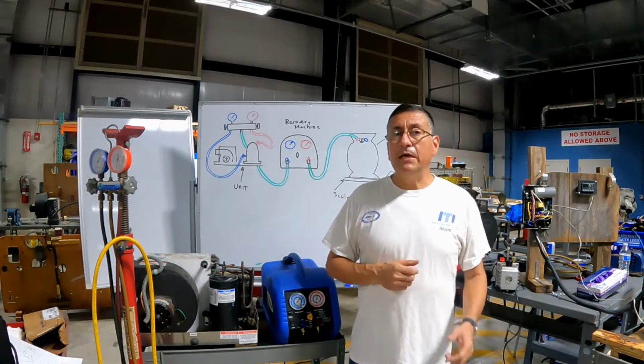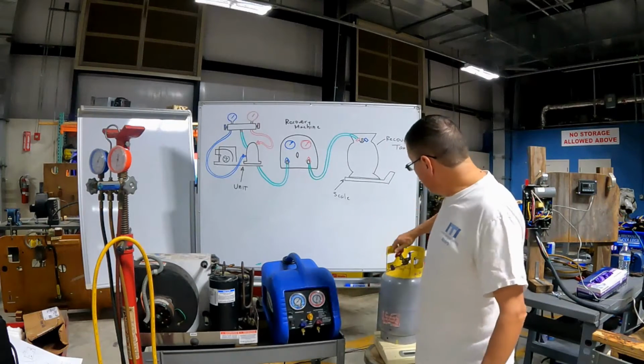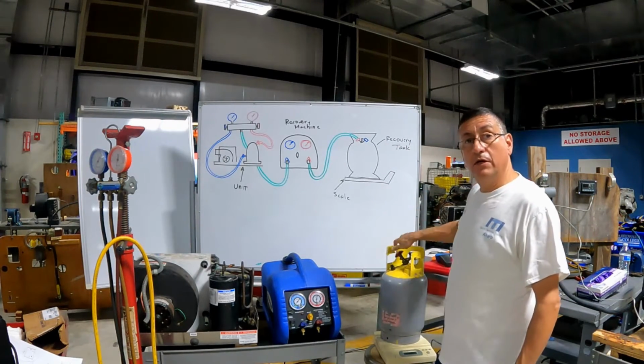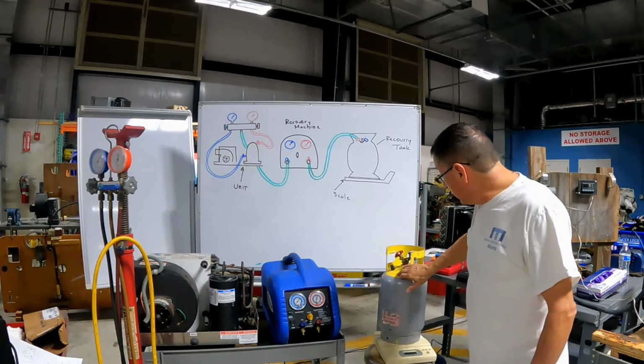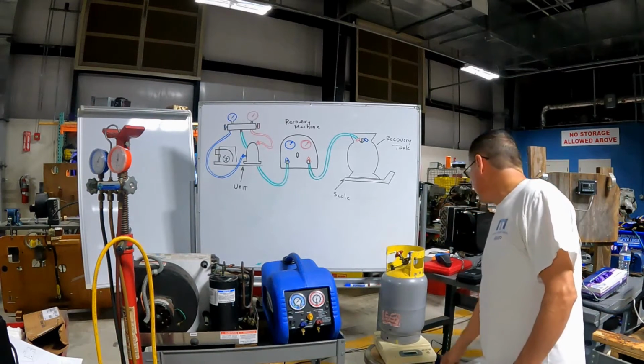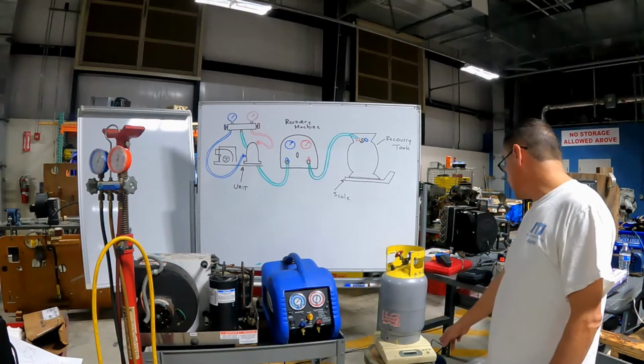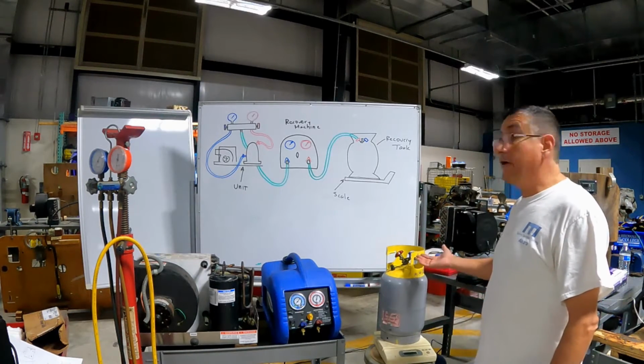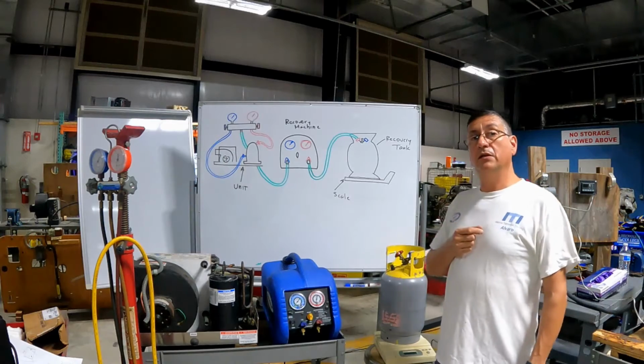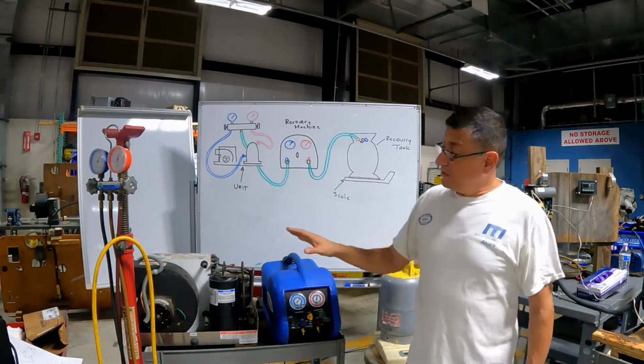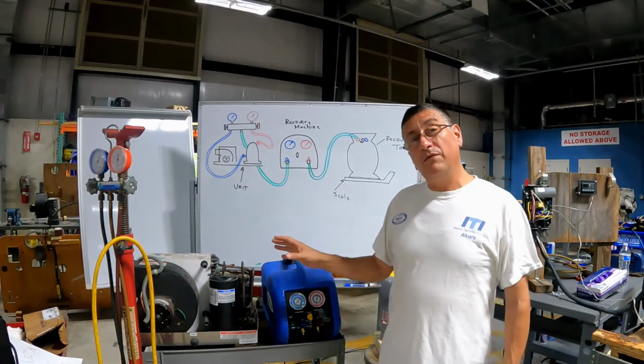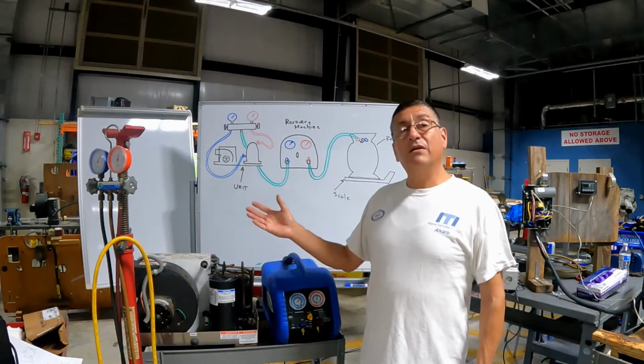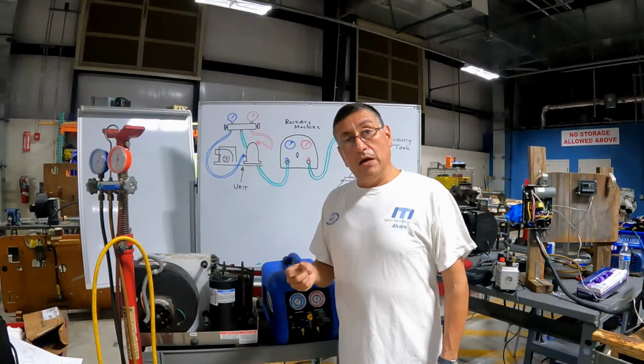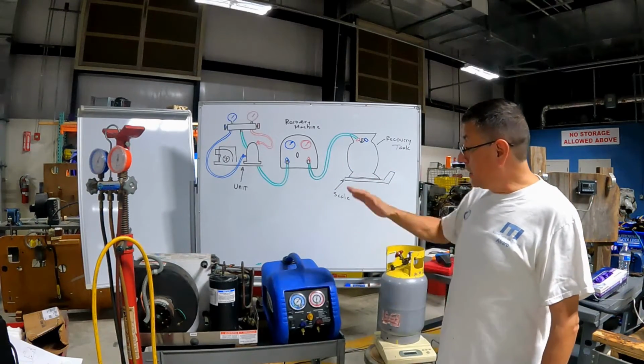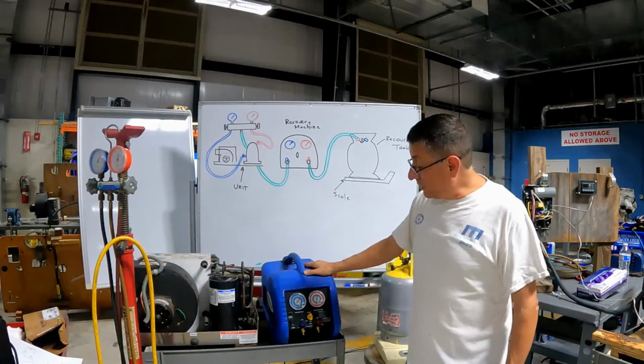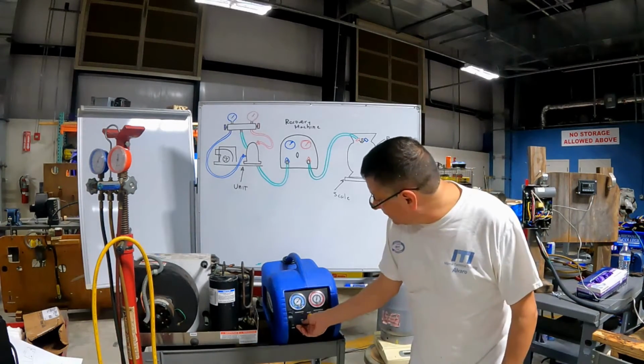Okay, the first step is to verify that the cylinder valves are off. Check the tare of the cylinder, how much the weight is, and verify the weight is okay, it is 19 pounds. Okay, we have enough space to recover the refrigerant of this equipment. At this moment, this equipment has lost a little amount of refrigerant, and we are going to recover the refrigerant that the equipment has. Okay, that's the procedure. At this moment, the recovery machine is off, and both valves are off.